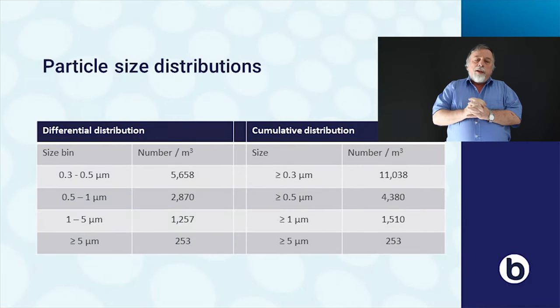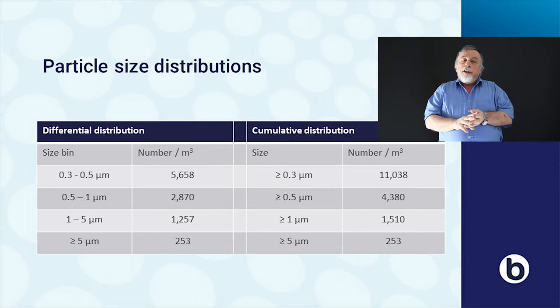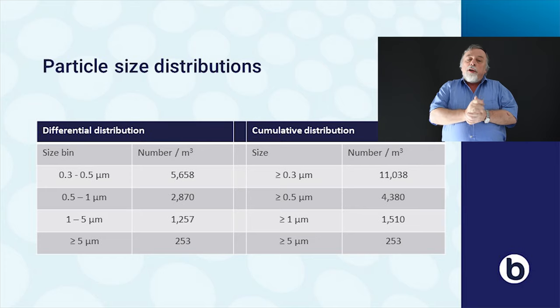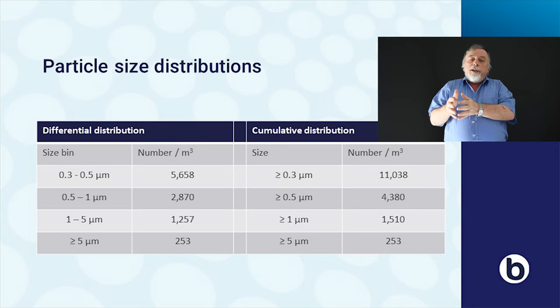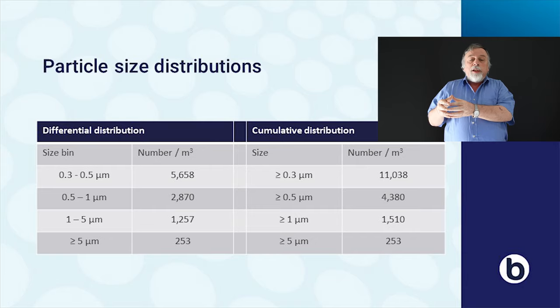In a particle counter you can have more size bins: from A to B, from B to C, from C to D. In the example table, A is at 0.3 micrometers, B at 0.5 micrometers, C at 1 micrometer, and D at 5 micrometers. On the left hand side you see a table with the particle size bins and the number of particles per cubic meter. On the right hand side you can see how we calculate a cumulative distribution by starting with particles larger than 5 micrometers and adding each successive size bin, giving you a particle size distribution which we normally use when talking about air cleanliness.